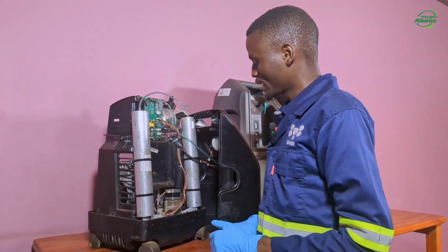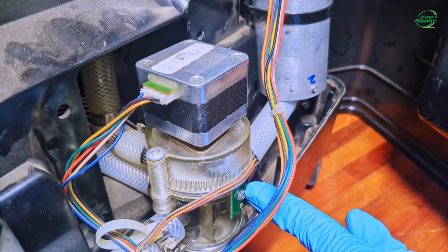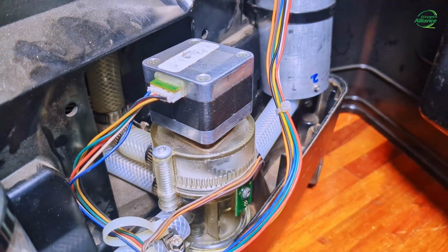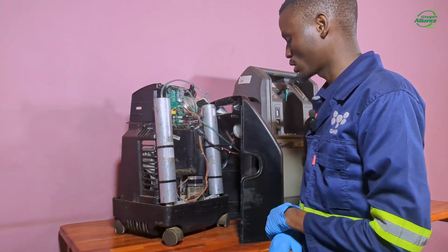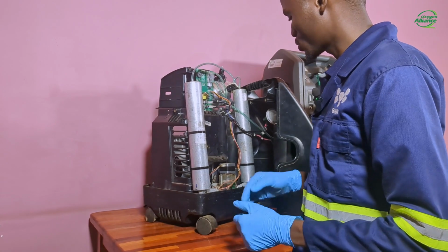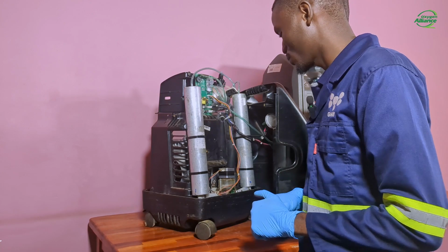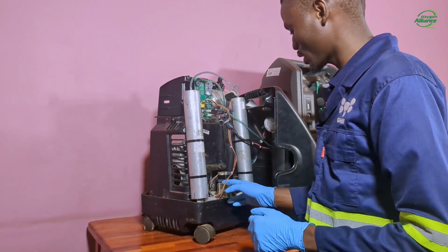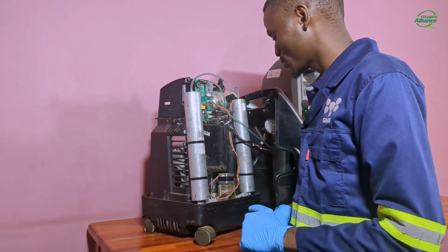Another problem that may arise with the valve is a misaligned Hall effect sensor. So this is our Hall effect sensor. The valve uses this sensor to identify its position. So any misalignment of the sensor may cause the valve to stop at incorrect positions, or in some cases, it may rotate continuously. So you just have to make sure that the sensor is properly aligned and also that the screw is tightened. You will find links in the description below of videos on how to service or replace the rotary valve.